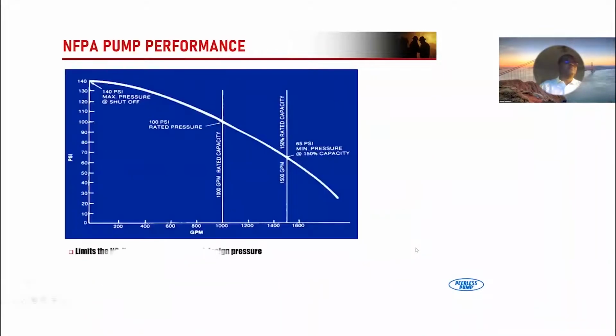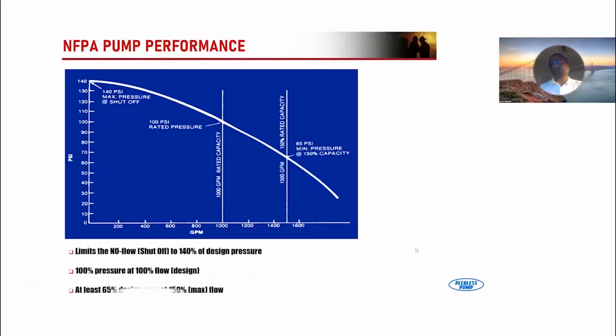So what are the, initially I mentioned NFPA 20. NFPA 20 requires that any pump be listed, this is the basic design requirements. The shutoff head cannot be more than 140% of the design pressure. And you have to provide 100% design flow at 100% pressure, and at 150% flow, your pump cannot deliver less than 65% of the design head.